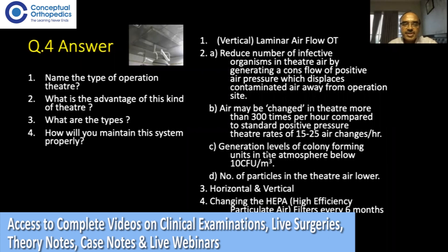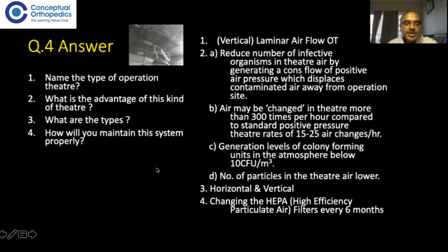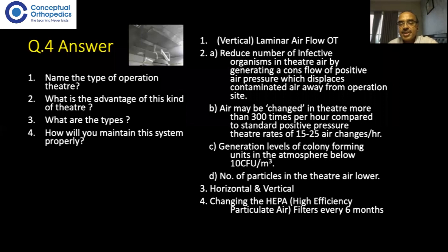There are two types of laminar airflow: horizontal, where units are mounted on side walls and require no major theater alteration, though horizontal laminar airflow is less effective; and vertical laminar airflow, which is the best. To maintain the system properly, the HEPA filters — high efficiency particulate air filters — must be changed every six months, and the whole system requires cleaning, so that the laminar airflow remains effective.